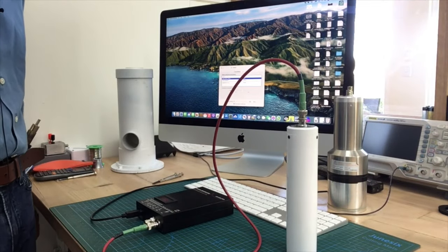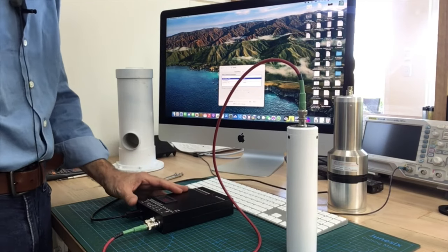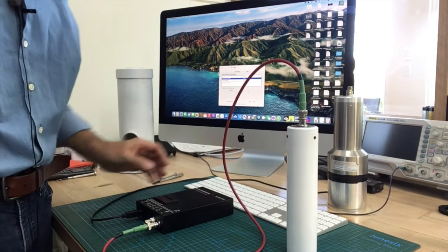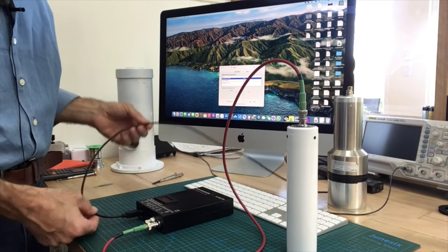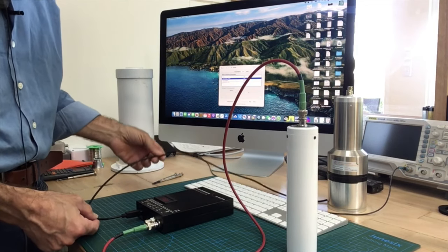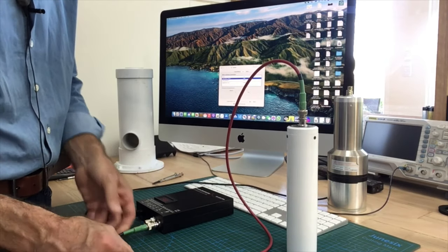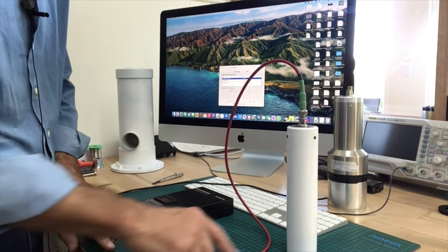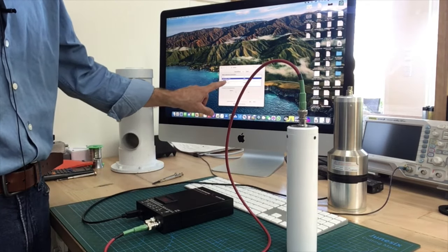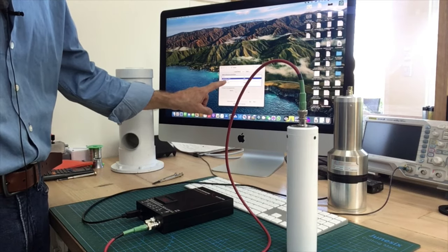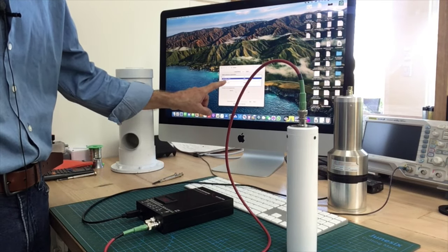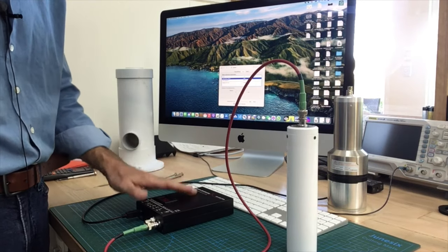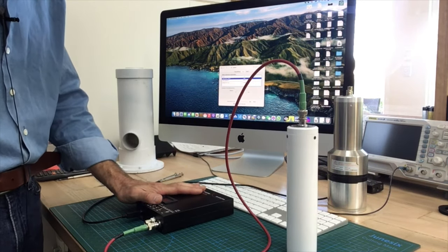Here we can see that I have the GSUSB Pro connected to the GS1515 sodium iodide detector, the USB cable connected to the computer, the SHV coaxial cable connected to the detector. So this is a single wire detector and the first thing I check here is that the sound card has shown up on my computer in the audio settings. That indicates that the computer has recognized the audio codec in the GSUSB Pro. So that will be your step number one.